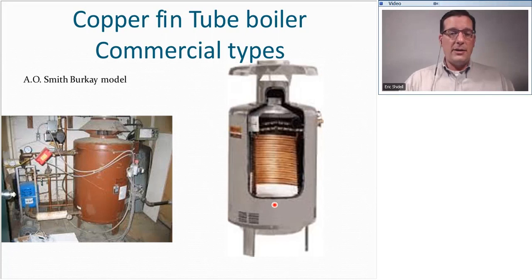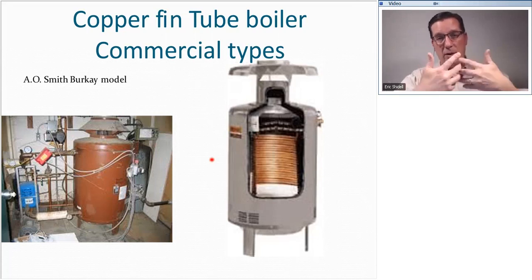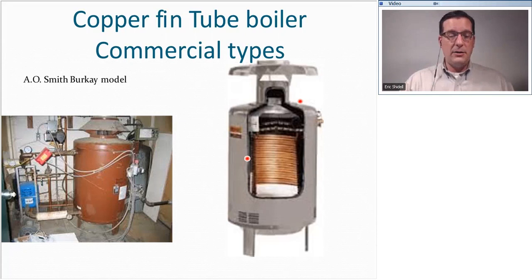So this boiler has this burner coming down here, and the products of combustion have to pass horizontally through the copper fins as they're wound around and around to get up and into the flue. You look at this boiler and you think, man, that thing looks like a disaster. There's just wires and stuff everywhere. Somebody really didn't do a good job on that. Well, that's the way they are. When you buy one of these, this is all you get. All this other stuff had to be field installed by the original installer. So all the wiring had to be done, and all the accessories had to be installed by whomever used their creative mind to decide how to put that together.